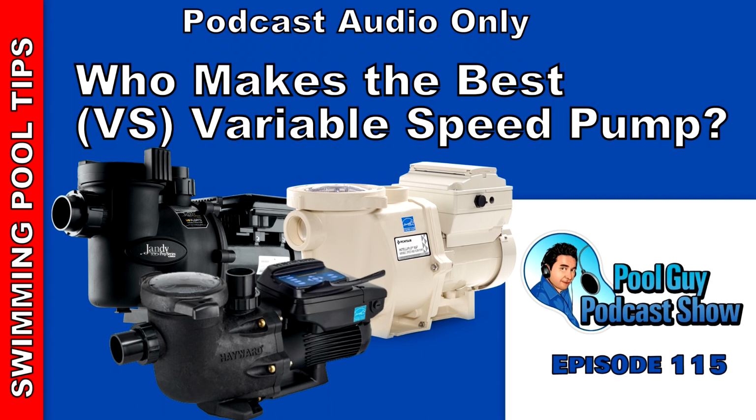So no matter what brand of pump you have, I think the only one it won't work on is like the gigantic Tristar pumps or the gigantic Jandy Jacuzzi pump. But a standard pump like a WhisperFlo or Super 2 or any of the Jandy standard speed pumps, you would just take the motor out and put the Century VS motor on with the controller on the back, and that would convert your existing pool pump into a VS pump without having to do any replumbing, because you're not removing the pump itself, you're just removing the motor from the back.